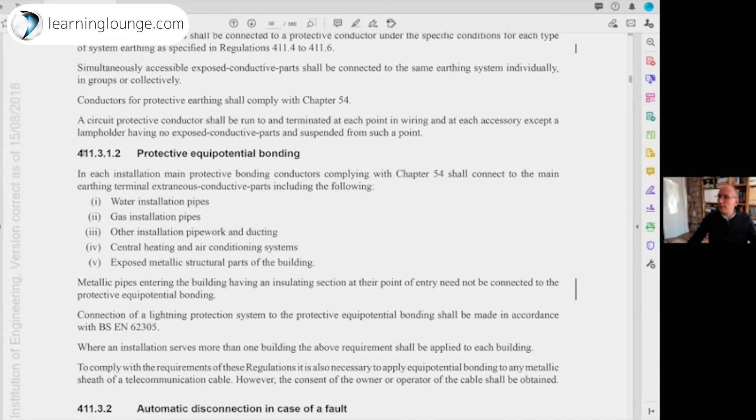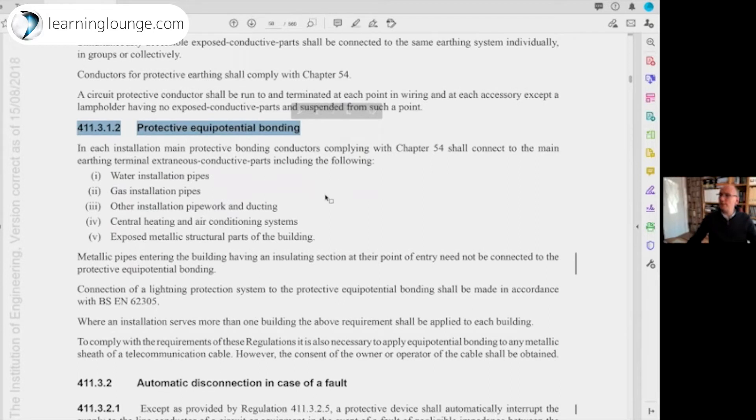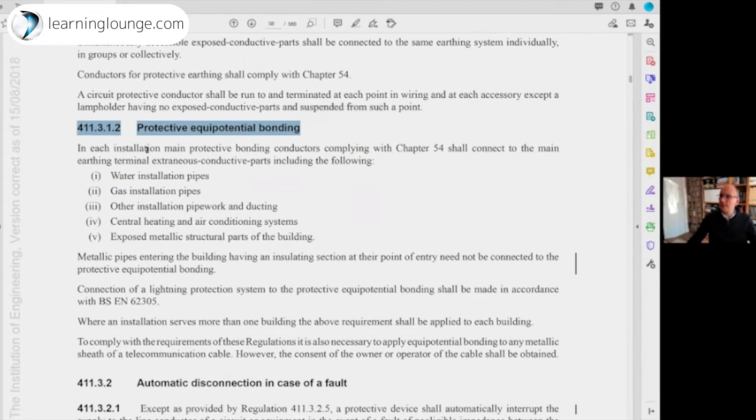Okay, there's two or three areas. Let me share my screen. Here I am at 411.3.1.2, protective equipotential bonding. As we can see, in each installation main protective bonding conductors complying with chapter 54 shall connect to the main earthing terminal extraneous conductive parts. It includes the following: water installation pipes, gas installation pipes, other installation pipework and ducting, central heating and air conditioning systems, and the exposed metallic structural parts of the building.